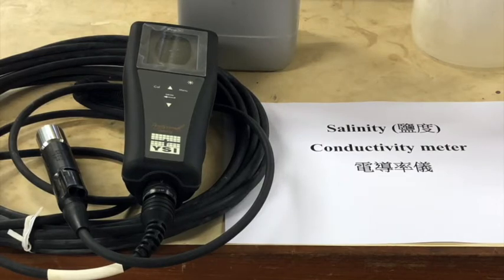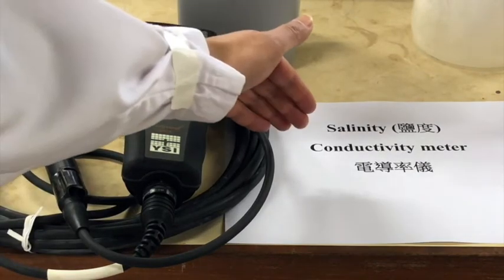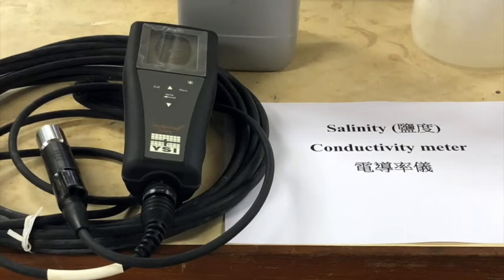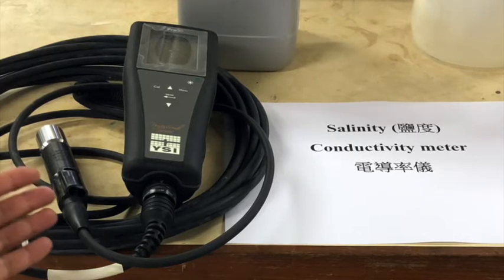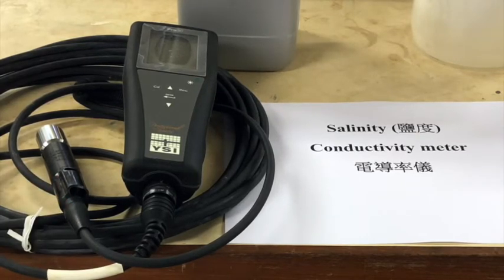This is the salinity meter. To be more accurate, it should be called a conductivity meter. The conductivity of the sample will be measured, and the conductivity of the solution is proportional to the amount of the dissolved salt. 0.01 molar potassium chloride solution is used as the standard solution for the calibration, as the solution has a specific resistance.